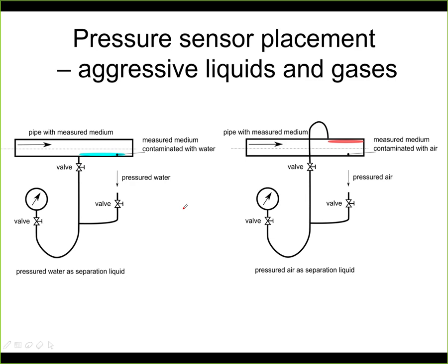Here is an example how you can do it in a pipe. So here we have the pipe with the measured medium. We assume that we may add some water in the medium. So if this is some gas, it's possible for technological reasons to add some water like this. And at the same time, we want to protect this whole system of the instrument from the damage caused by the medium. So this will not be damaged by the gas that we have here. So here this whole system is filled with water. So we need pressurized water. This valve and this valve serve us to disconnect the water and the system, and this valve allows us to disconnect the pressure gauge.